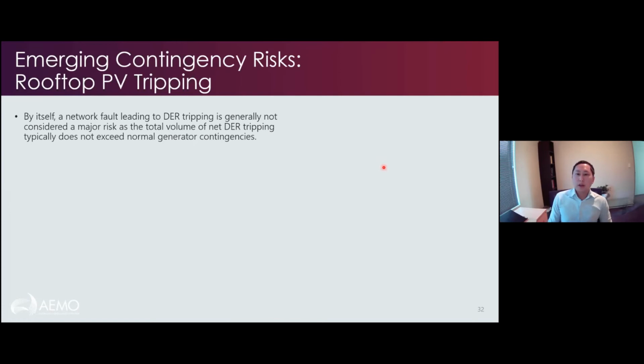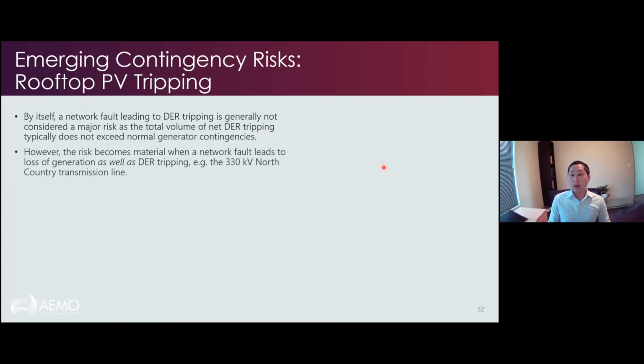So by itself, a network fault that leads to DER tripping is probably not a huge risk in the SWIS because we do carry a lot of reserves for large generator trips. Our largest generator is 340 megawatts, and often our generator contingencies are above 200 megawatts. So we are carrying enough spinning reserve for these contingencies. So if DER were to trip by itself, unless it was just a major fault somewhere that took out a lot of DER, then we don't consider that a huge risk. However, it does become material when a network fault also takes out generation as well as DER.